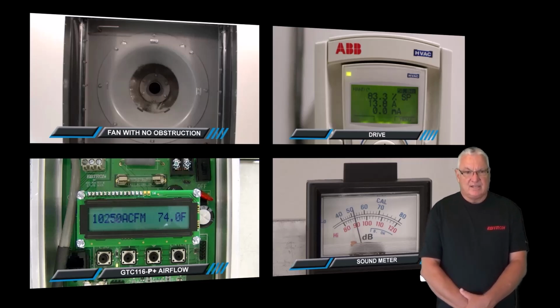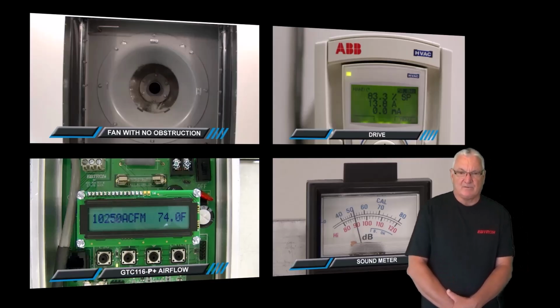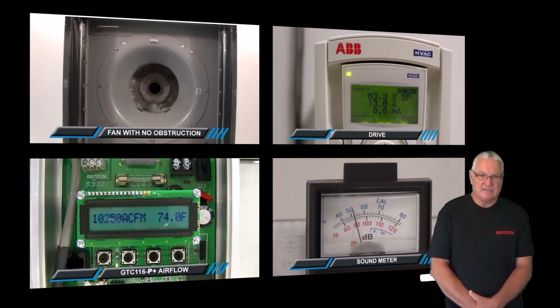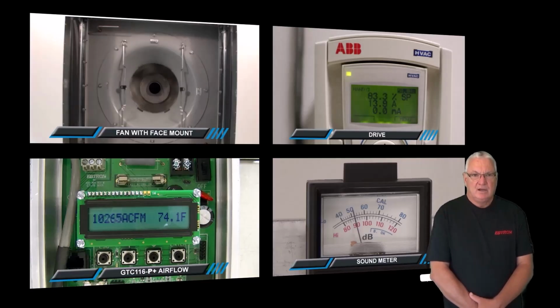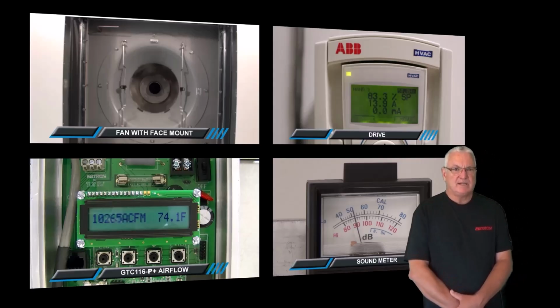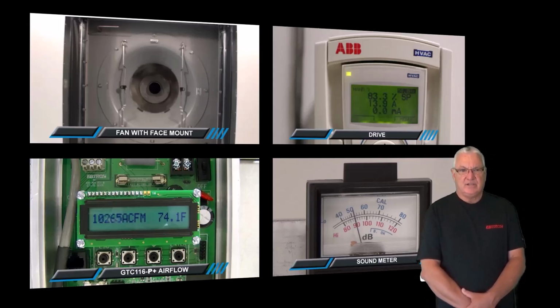Okay, at 10,250 CFM. And then the sound level is us having a sound meter upstream of the fan. It's kind of an arbitrary location we picked, but it's just right upstream of the fan. And that's 90 dBs, okay? We put in our flow meter, which is made for these plenum fans, and you'll see there's really no difference.